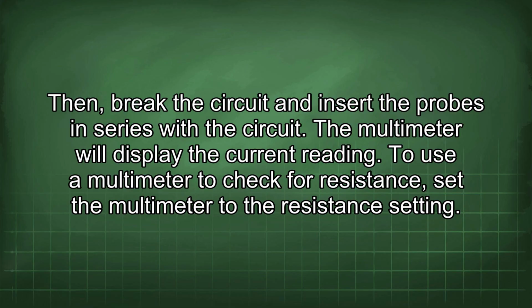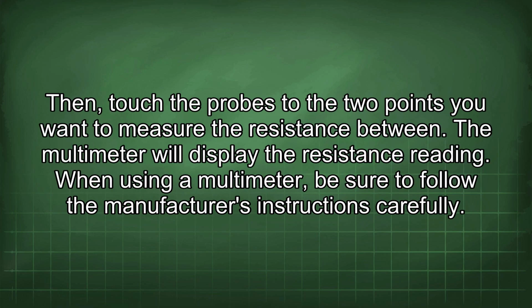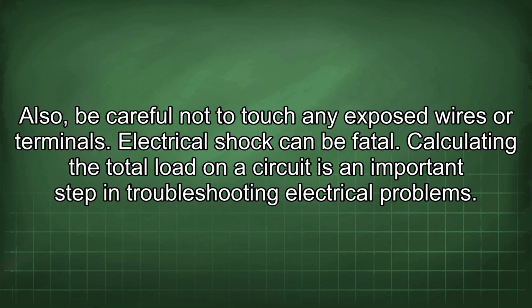To use a multimeter to check for resistance, set the multimeter to the resistance setting. Then touch the probes to the 2 points you want to measure the resistance between. The multimeter will display the resistance reading. When using a multimeter, be sure to follow the manufacturer's instructions carefully. Also, be careful not to touch any exposed wires or terminals. Electrical shock can be fatal.